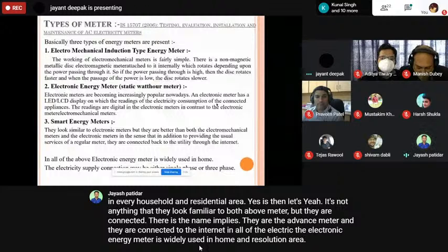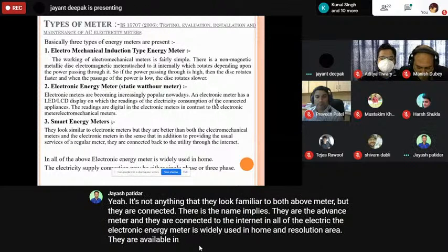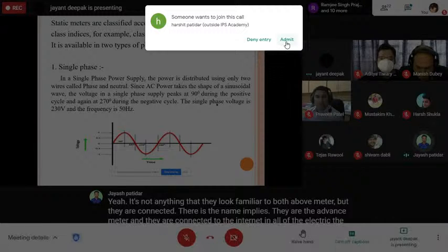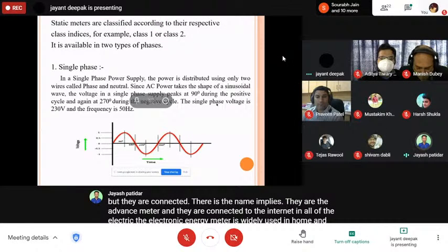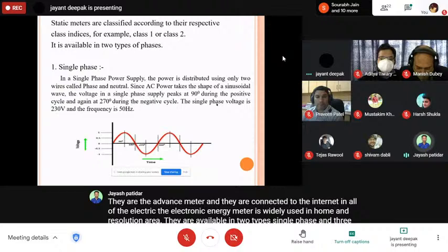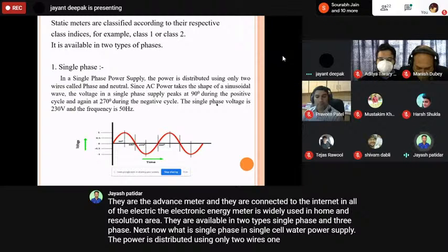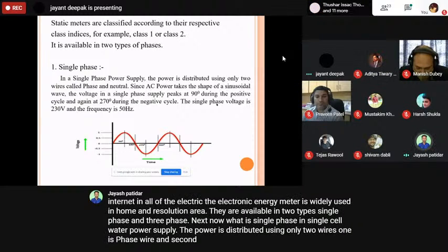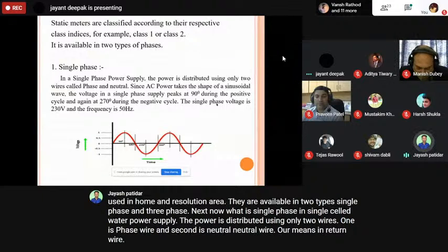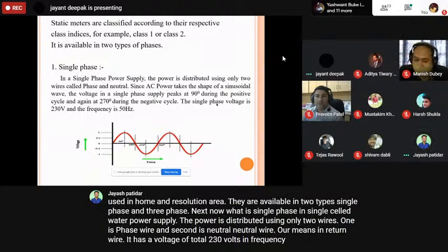They are available in two types: single phase and three phase. Next, what is single phase? In a single phase power supply, the power is distributed using only two wires. One is the phase wire and the second is the neutral wire, meaning the return wire. It has a voltage of 230 volts and a frequency of 50 Hz.